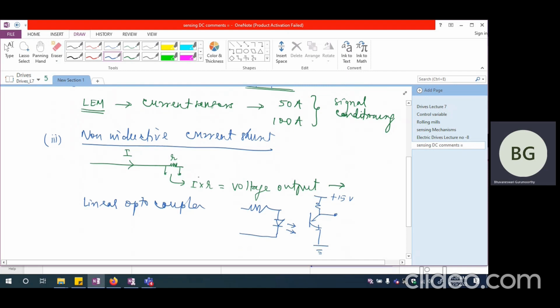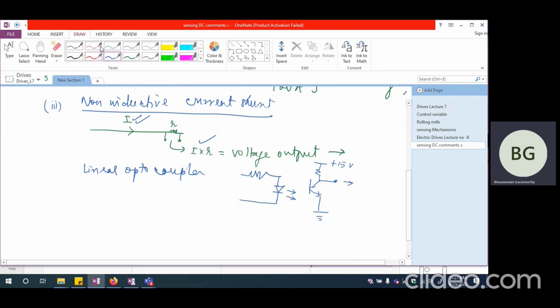So in which case, whatever is I multiplied by R, the corresponding output will be observed here, and you should be able to directly say that the output of the optocoupler is proportional to whatever is the current that is being carried by the conductor. But the only thing you have to remember is that there is isolation now existing between the main conductor, that is the power, and the measuring circuit. So that is the major advantage. So in a non-inductive current shunt, you need to provide isolation. If you don't provide isolation, any fault that occurs on the power side can affect the electronic side adversely and vice versa. That is the reason why we need to have isolation. And the isolation is generally provided by a linear optocoupler.